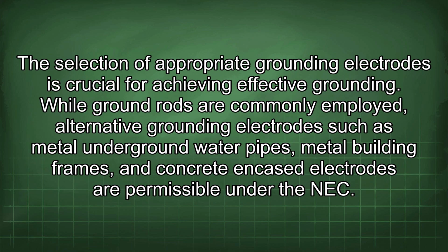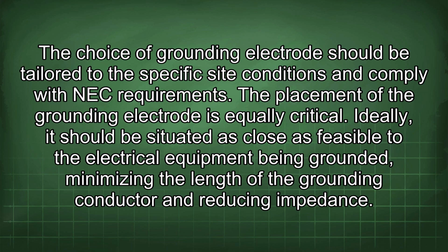The selection of appropriate grounding electrodes is crucial for achieving effective grounding. While ground rods are commonly employed, alternative grounding electrodes such as metal underground water pipes, metal building frames, and concrete encased electrodes are permissible under the NEC. The choice of grounding electrode should be tailored to the specific site conditions and comply with NEC requirements.